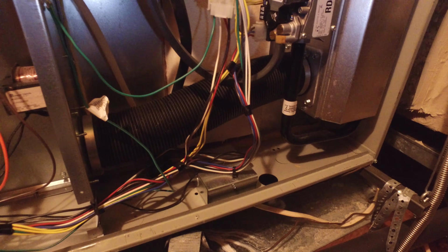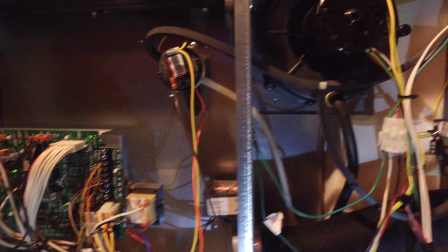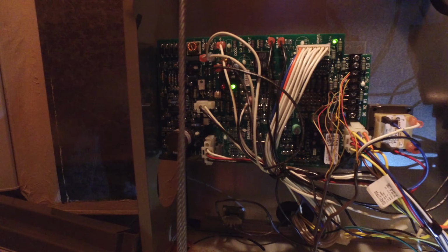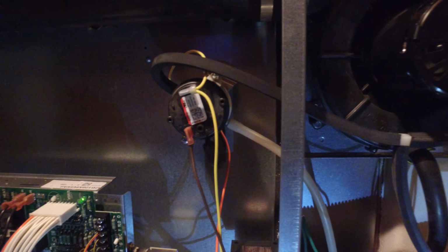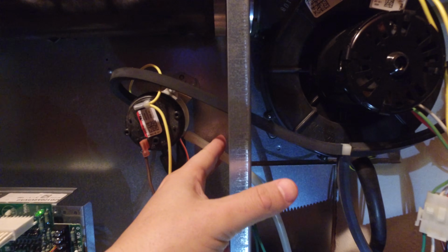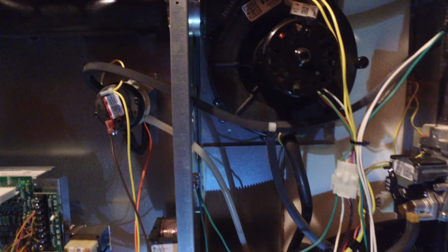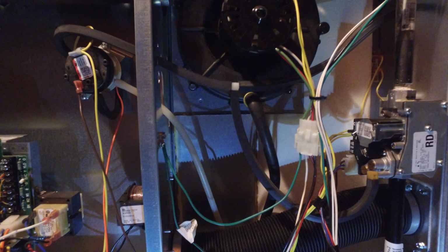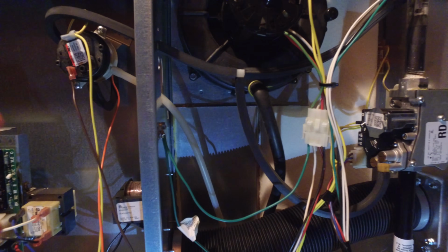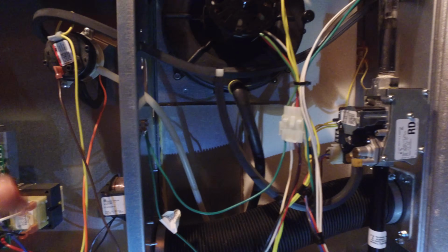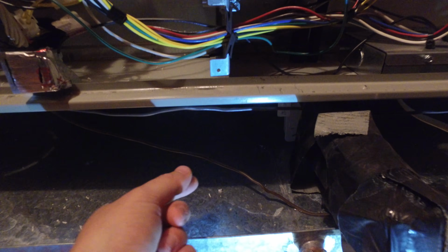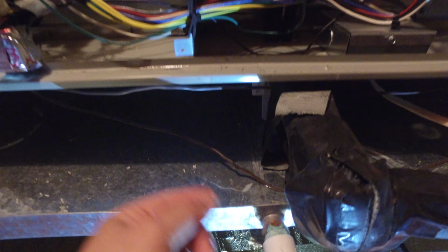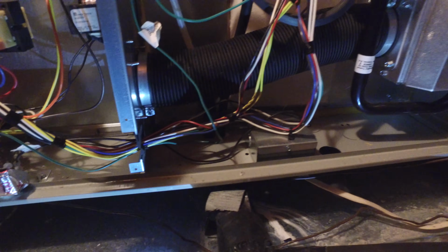So what ended up happening was, since that was clogged, we were getting an error code on the board. This red LED was blinking 3 times and then off. This vacuum switch has a little hose right here. He pulled this hose off and basically blew into it with his mouth, and you can hear the bubbling and gurgling. What we did was we brought that hose down here and drained it in this pan. So there was definitely water in here.